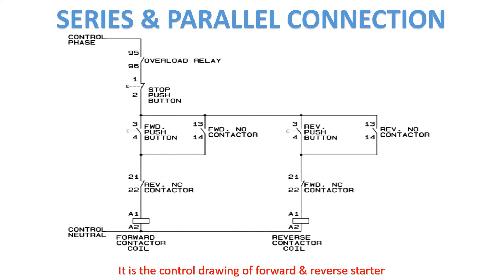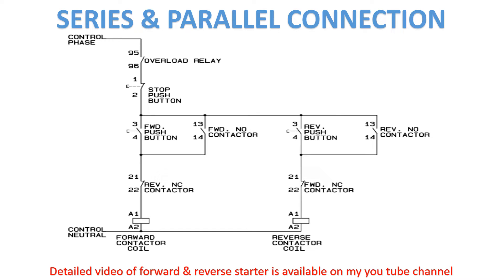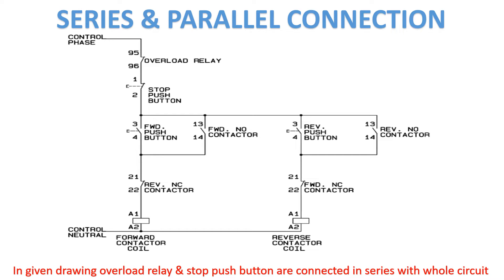It is the control drawing of forward and reverse starter. In the given drawing, overload relay and stop push button are connected in series with the whole circuit.